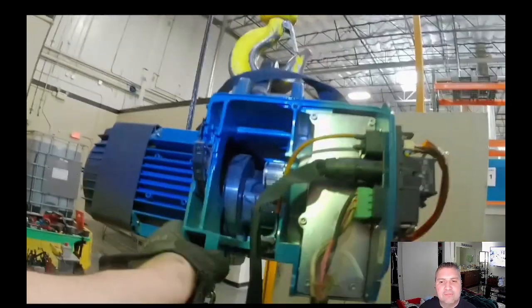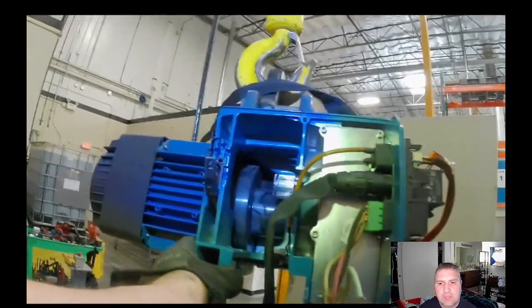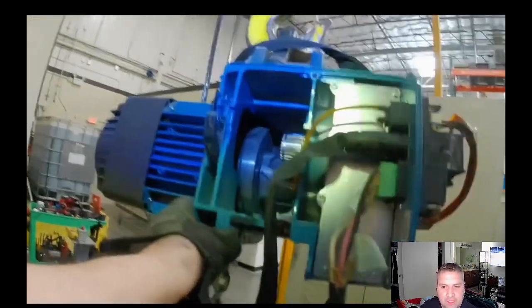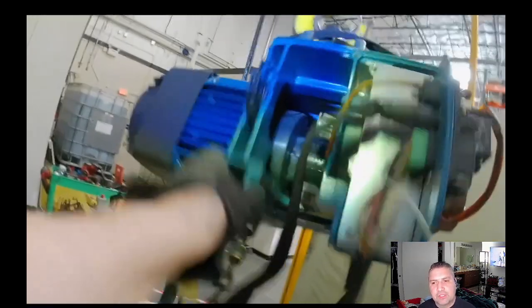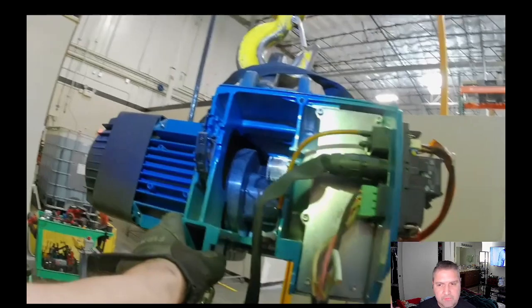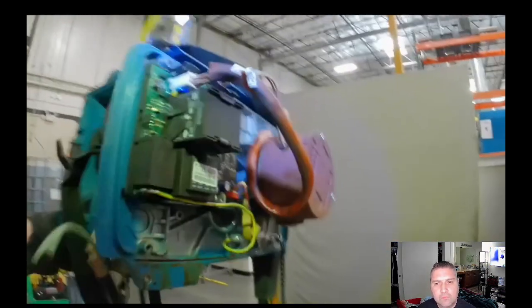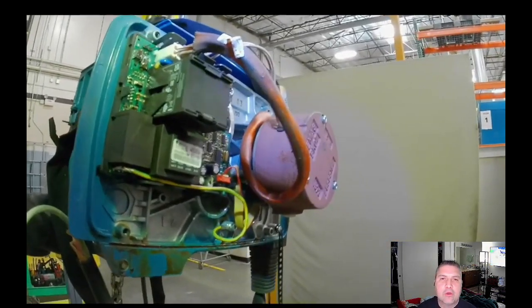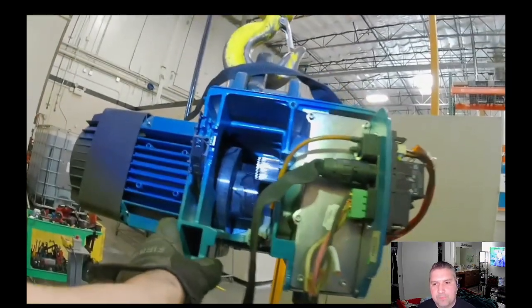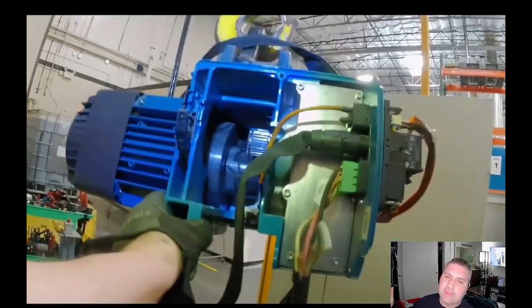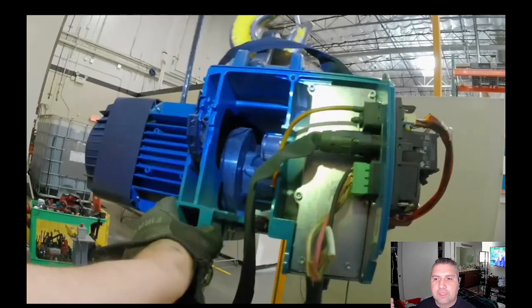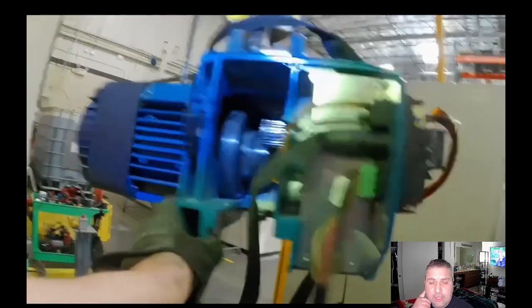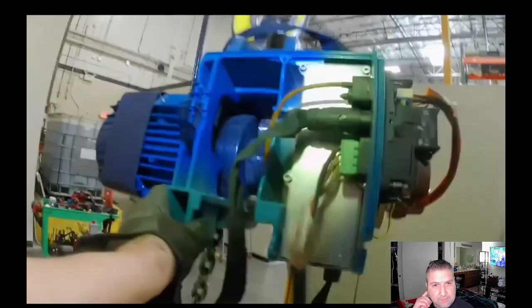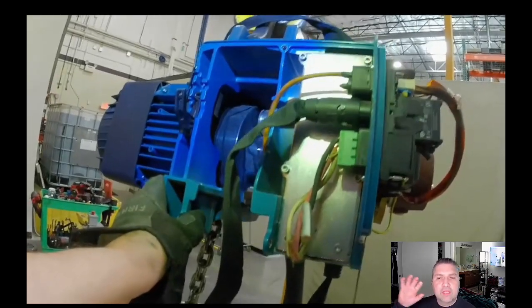So now I'm gonna test it with the new board. I tested the direction that I know is functional, and now this is the reverse direction. So both directions are functional with this other used board, which is virtually the same board. So I know for a fact that the board is bad. So based off this information, I'm gonna go ahead and get a quote for a new board, and as soon as I get it, I'll come back to this facility and replace that board, get this hoist functional, and then I can put it in their inventory.